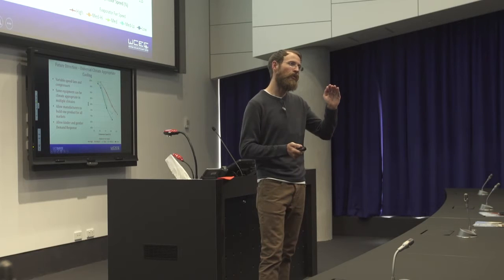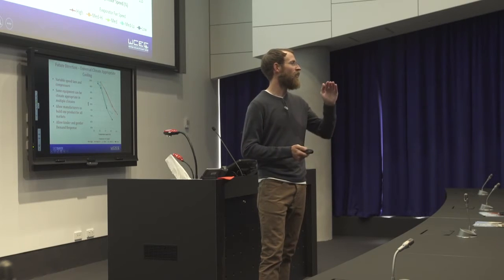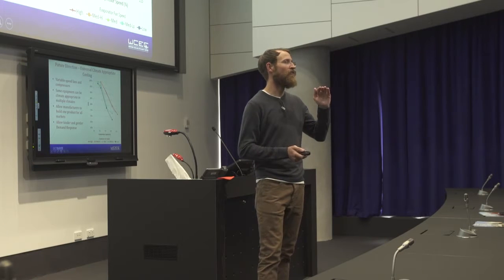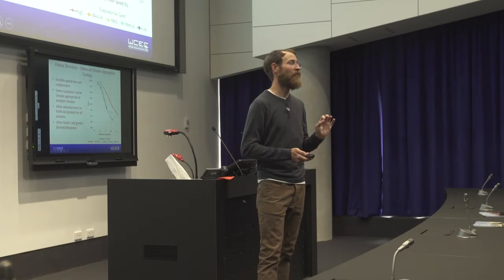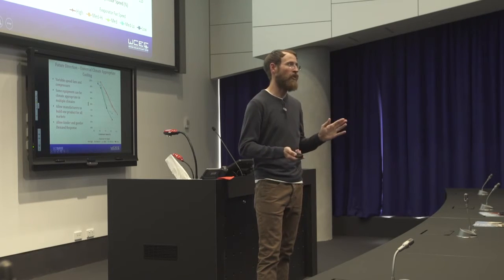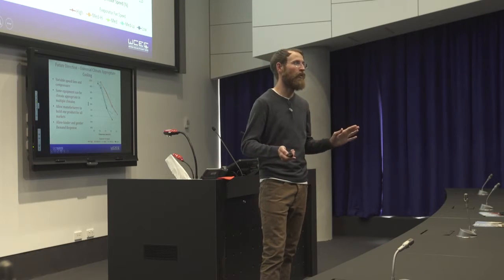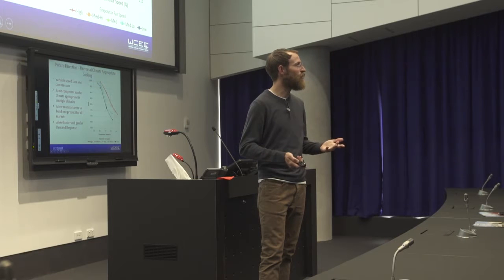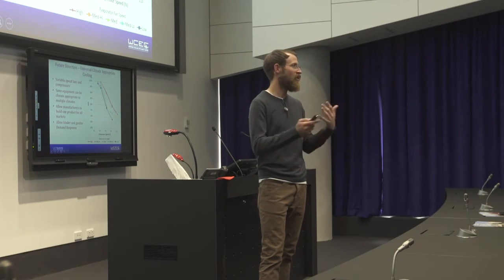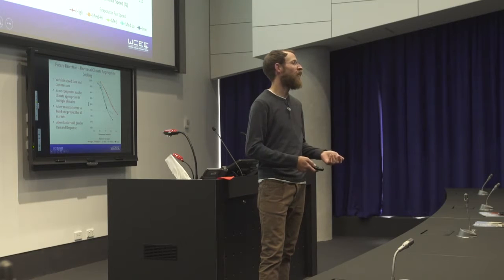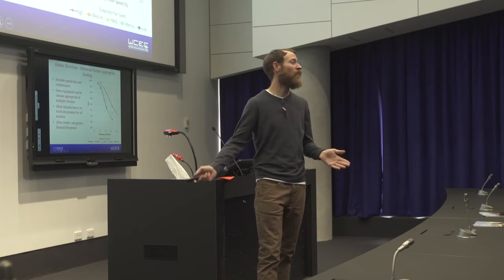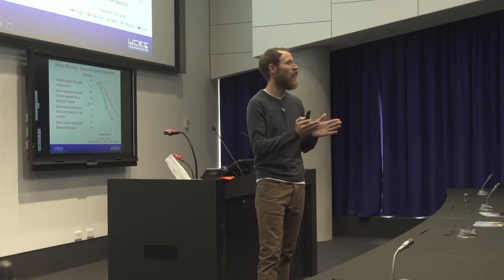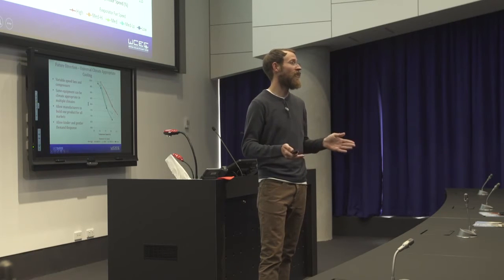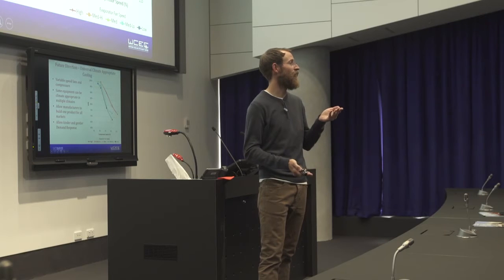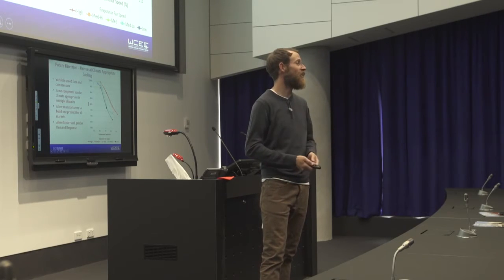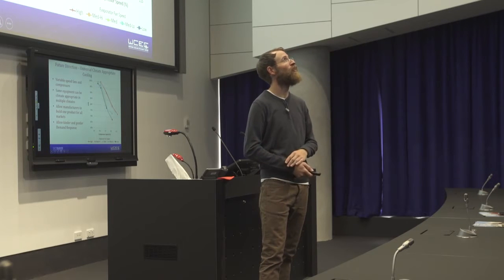Especially, you can tune the sensible heat ratio of the system. Now, in hot, dry climates, we would argue that it's very rare you actually need to be doing dehumidification. Quite often, you can get away with not doing any dehumidification, reach your comfort points just fine. But because of the way vapor compression systems usually operate, there's a considerable amount of moisture that's removed from the air. When we do all of our assessments, we discount all of that energy that goes towards dehumidification. We look at the sensible only capacity of the system. And we're finding that there's ways to tune the compressor speed and the fan speeds such that you can optimize that sensible heat ratio and do as little dehumidification as possible.